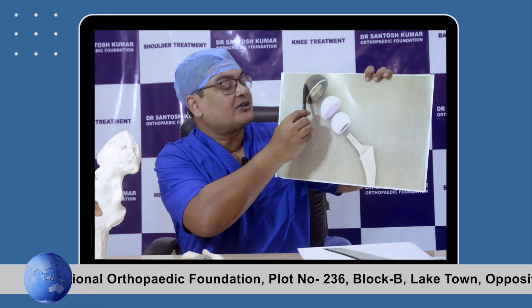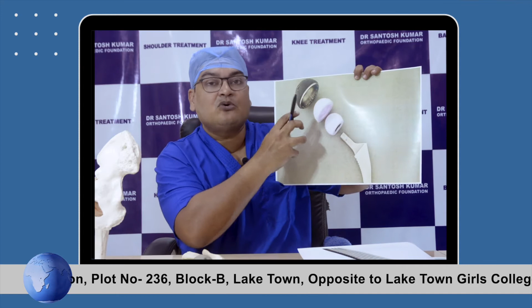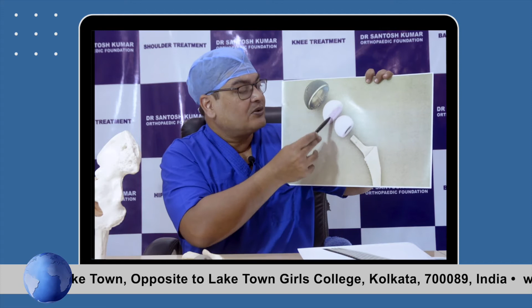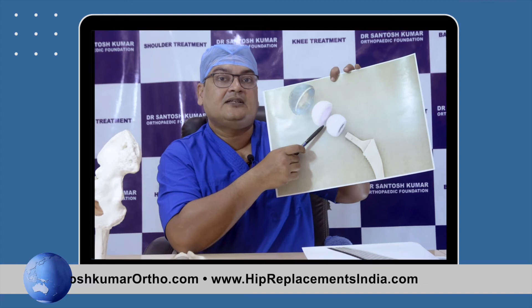And this is the metal shell, which is again highly porous coated, and it has holes for screws, so that it can be fixed in the bone with additional screws if needed, or many times we fix it preventively. So this liner can be ceramic or polyethylene. I personally prefer polyethylene because I prefer a hard on semi-hard surface. If both the head and the liner are ceramic, it may cause a squeaking sound. So I prefer polyethylene.